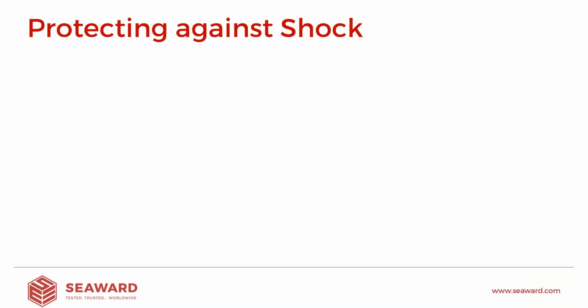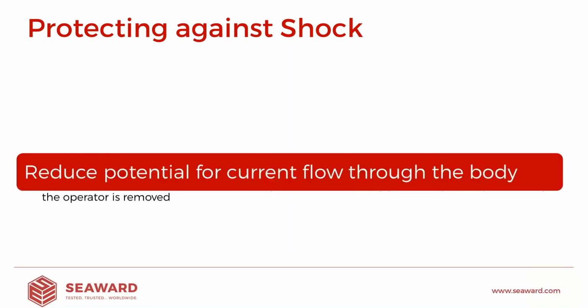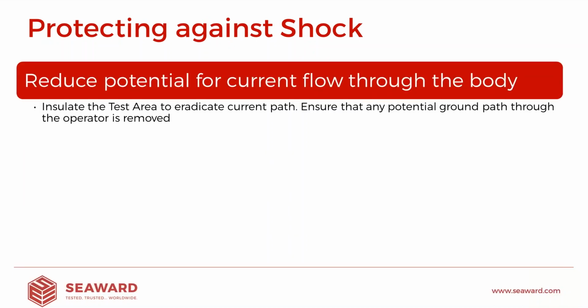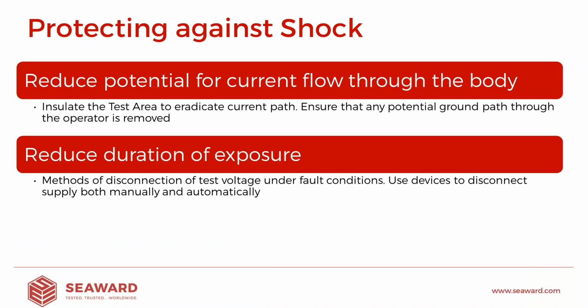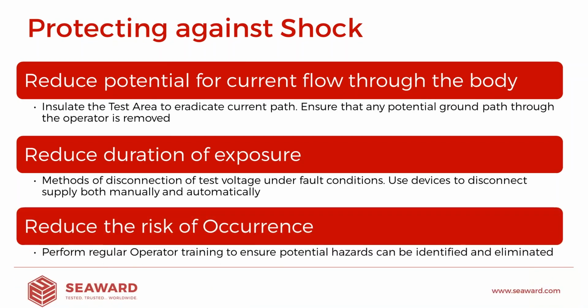And really there are three things we can do to protect ourselves against shock in an electrical test environment. Firstly, we look to simply reduce the potential for current flow through the body. In order to do that, we look to eradicate any current paths. So can we take away any potential ground path through the operator? We'll discuss ways of doing that as we move through the presentation. Secondly, we can look to reduce the duration of the exposure. So have we got methods of disconnecting the fault currents in the event that something was to go wrong? Those devices could be manual disconnects, so things like emergency stops, but they could also be automatic methods of disconnection. And ultimately, we can look to reduce the risk of occurrence happening at all. We can do this by training the operators to understand the hazards involved in their job, to be able to spot those sorts of problems that could cause an electric shock. And hopefully through good training, we can eliminate the risk.